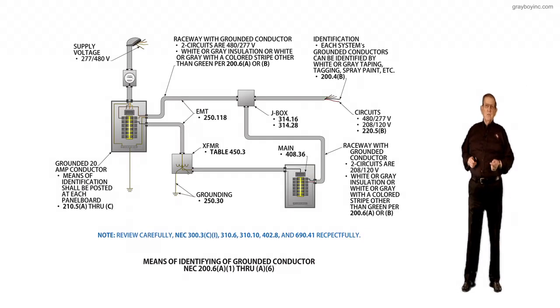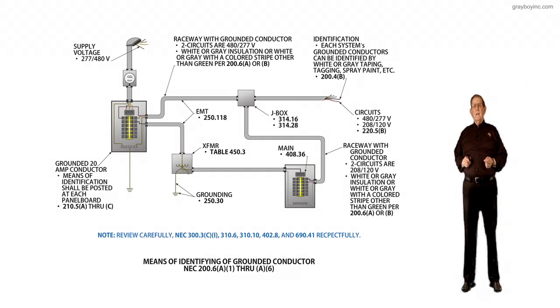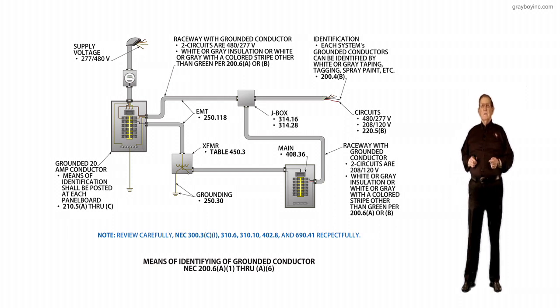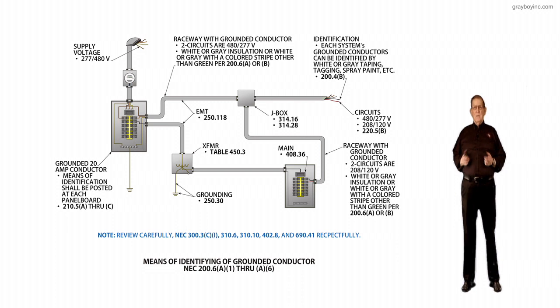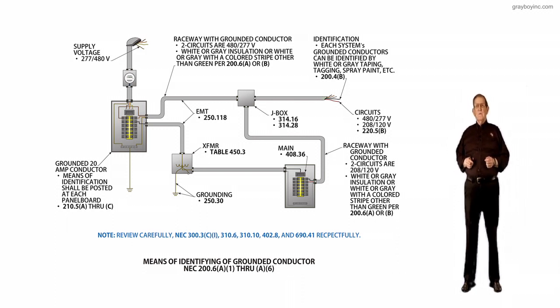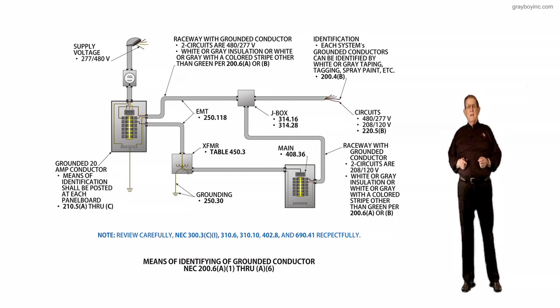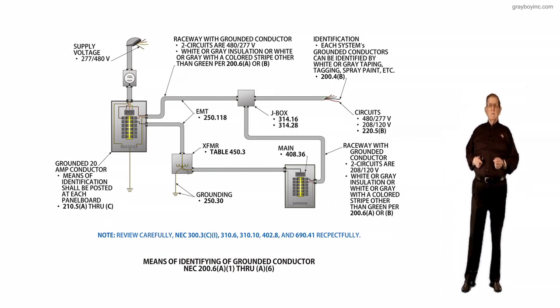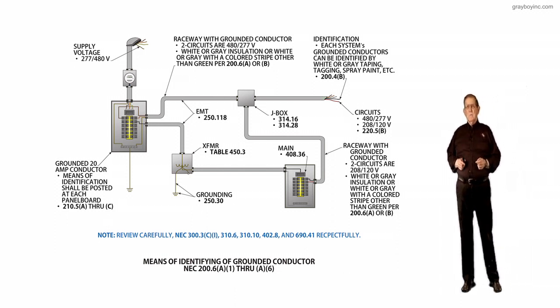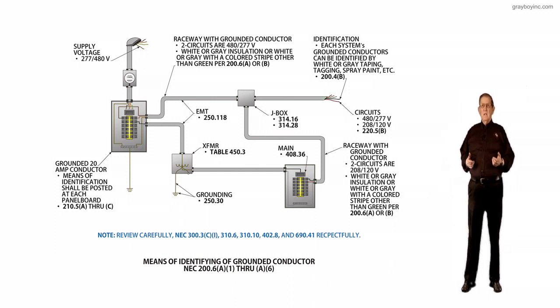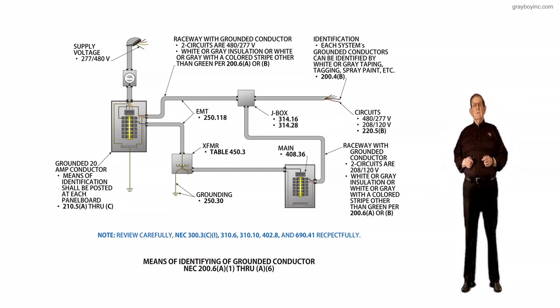This illustration deals with means of identifying the grounded conductor. 200.6A1 through A6 addresses the grounded conductor. Purpose of change: a revision has been made to clarify that the termination marking requirements are similar to other applications where the grounded conductor might be involved.